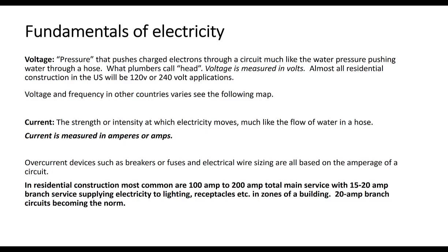In residential construction, referring to single-family homes, the most common setup is 100 to 200 amp total main service to the house, with 15 or 20 amp branch circuits supplying electricity to lighting, receptacles, and different zones of a building. 20 amp branch circuits are becoming the norm.